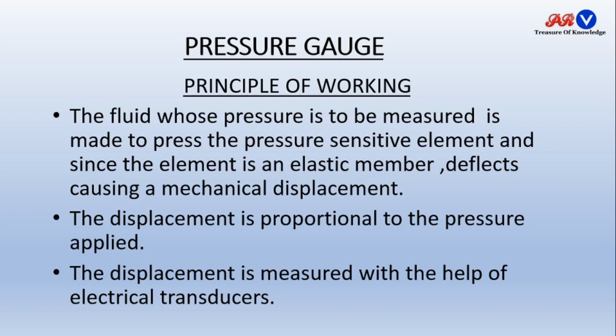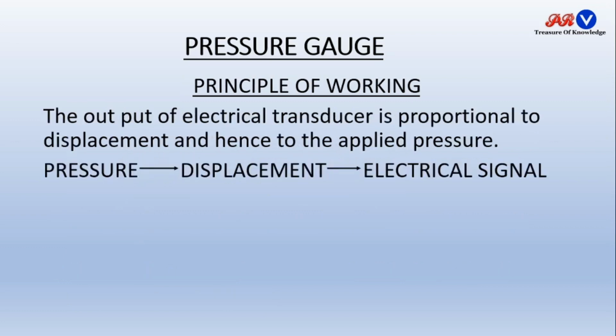The displacement, second point, the displacement is proportional to the pressure applied. Naturally, whatever displacement occurs in the elastic material is proportional to the pressure applied in the Bourdon tube. The displacement is measured with the help of electrical transducer, or instead of electrical transducer we can use a pointer and scale arrangement, which is calibrated, that gives directly pressure on the scale. This is the simple principle of working, which is very simple.